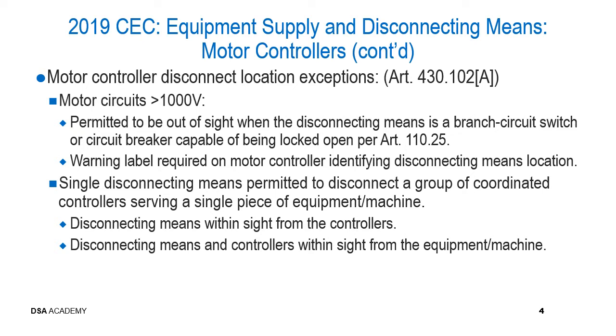Another situation is a single disconnecting means is permitted to disconnect a group of coordinated controllers serving a single piece of equipment or machine. In this situation, the disconnecting means is required to be within sight from the controllers. The disconnecting means and the controllers are required to be within sight from the equipment or the machine.